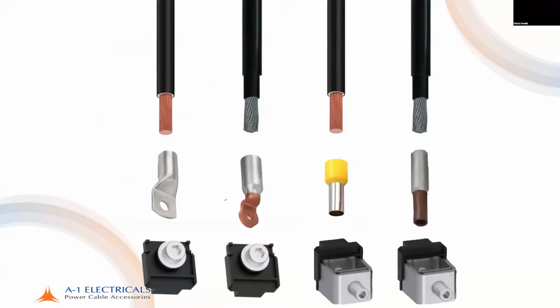Yeah, see, basically it depends on the switchgear and your conductor. If your conductor is aluminum and the switchgear bus bar is aluminum, you can use aluminum lugs. In the same way, if your conductor is aluminum and the switchgear has a copper bus bar, you need to use a bimetallic cable lug, so that the palm is copper, connecting to the copper bus bar, and the barrel is aluminum, so it has no galvanic reactions. And if the conductor is aluminum and the switchgear bus bar is also aluminum, you can use the aluminum lug. So it all depends on your connection, what the bus bar is and what the conductor is. According to that, you need to select your lugs.